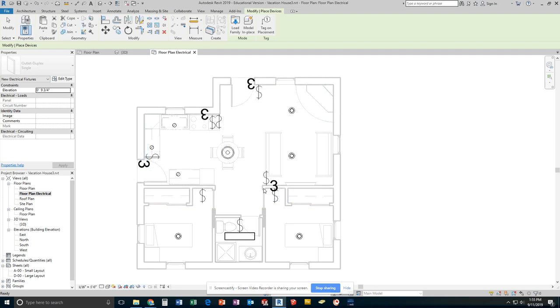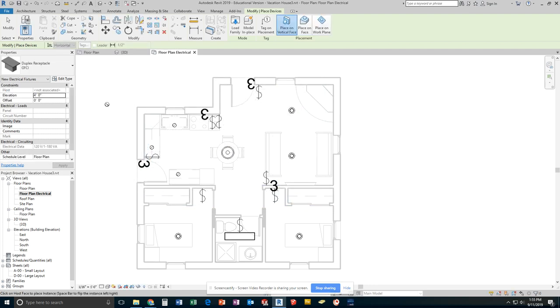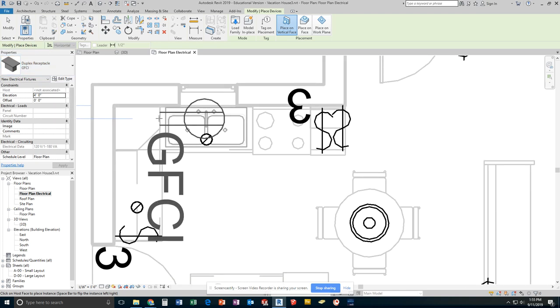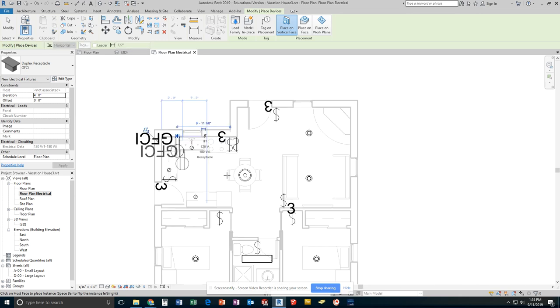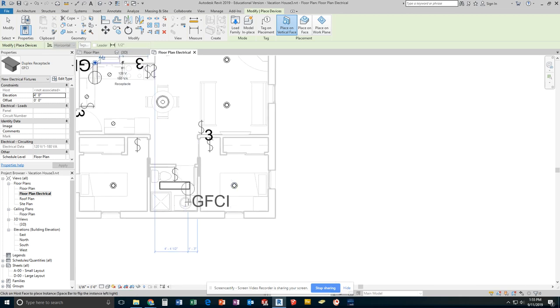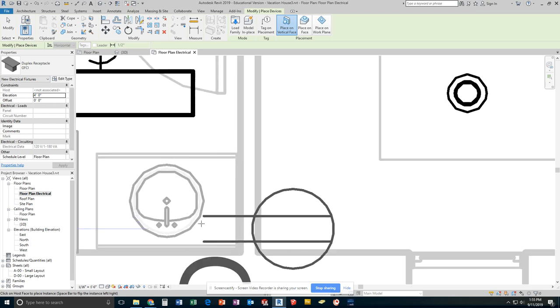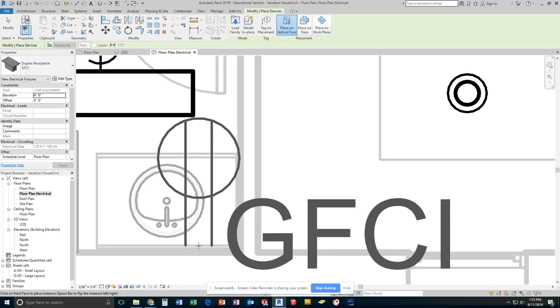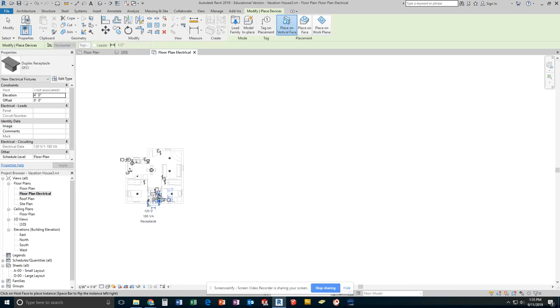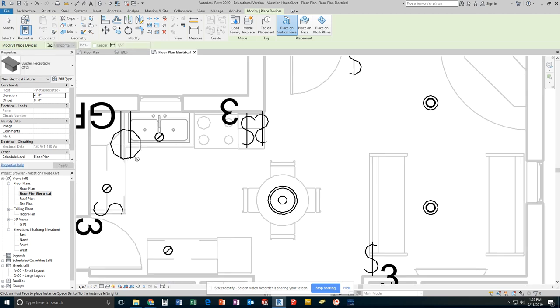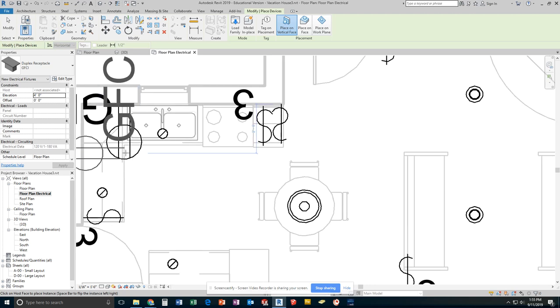These are our standard plugs where they have two different plugs. Right now, it's giving me a certain type called a GFCI. I will need one of these in the kitchen, so I'm going to put it near the sink. And I'm going to need to use this style of outlet in the bathroom. GFCIs are used in any wet location. You don't need to do all GFCIs in your kitchen, but you need at least one. They actually can be hooked up together.